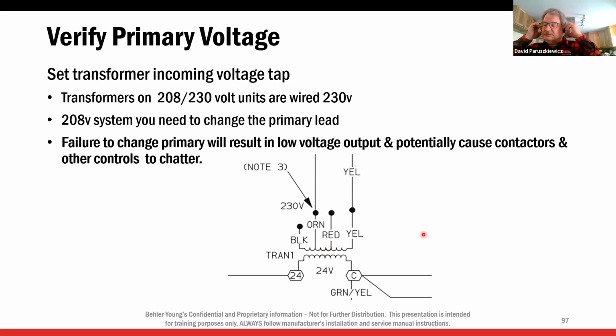So first thing you should do, check your voltage. If I have 208 going to the transformer, make sure you set it up accordingly. If I have 230, make sure you set it up accordingly. What if I'm sitting at 219? Well, check it both ways. And whatever way you get the highest on the secondary side, that's where we should be. Now, I don't mean, it's 208, so set it for 230, because then we're going to be too high. But if you're not sure, 219 is in between. Which one do I use? We should have 26, 27 volts on the secondary of the transformer. But make sure you do this. I can't tell you how many times I've been on jobs where the contactors are chattering, burning contactors out, economizer issues, and it all relates to this.